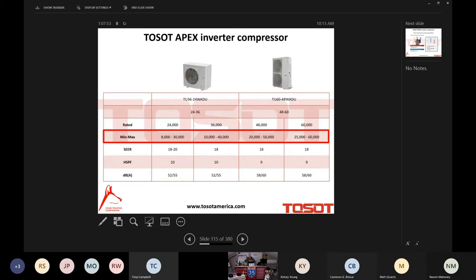24,000 BTU system, look at this now, can give you as little as 8,000 BTUs, but as much as 30,000. My friends, that's one system with that complete range of capacity from 8,000 to 30,000. Let's go to the other end of the spectrum. The 60,000, the 5-ton system, can give you as little as 25,000 BTUs, but as much as 60. One system. One system with that complete range of modulation, with that complete range of capacity.